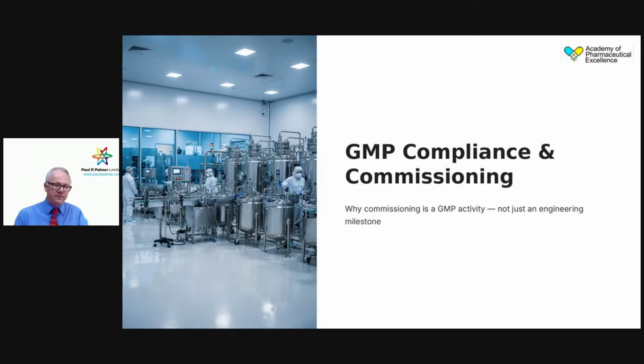You're going to have to do an update, change what's installed, and once it's installed, it's going to cost a lot more. If you can get the design right at the supplier during commissioning, you're going to save yourself a lot of money down the line. But not only that, you're going to have the evidence to show you verified the design in advance—provided you're taking the pictures, writing the documents, recording the notes, and verifying against your acceptance criteria. When you verify it, write it down, sign it, date it. And if you've got to measure something, use your calibrated equipment while you're there.